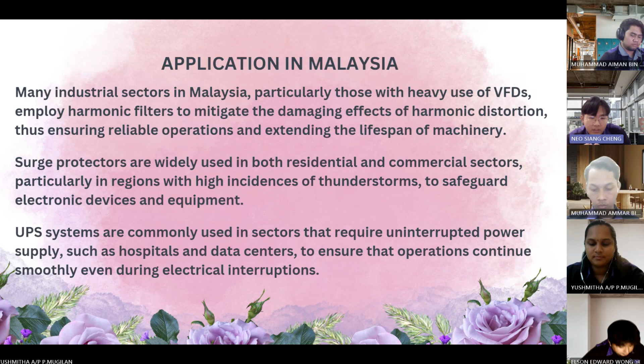So for case study, addressing the harmonic distortion in a manufacturing plant, the problem is a manufacturing plant in Malaysia faced excessive harmonic distortion due to the use of variable frequency drives. This caused overheating in transformers and equipment malfunctions. The solution is the plant implemented a combination of passive and active harmonic filters. The passive filters were effective in addressing the lower order harmonics, while active filters were used to target higher order harmonics specific to the VFD. The outcome is the harmonic distortion was greatly reduced, resulting in fewer equipment failures and lower maintenance costs, and improved the overall operational efficiency. Next.